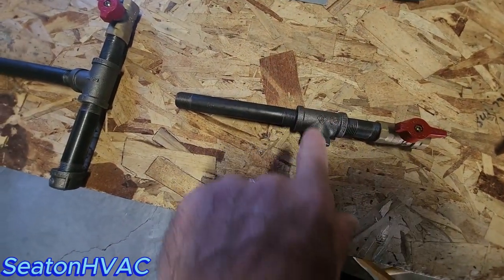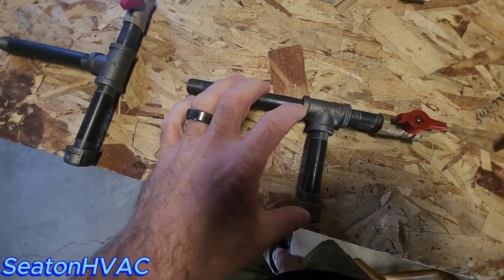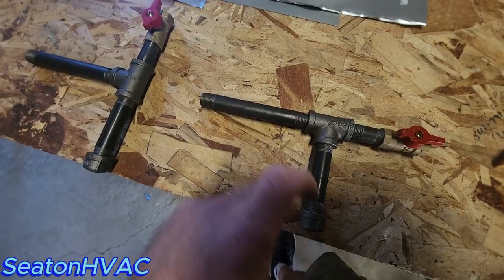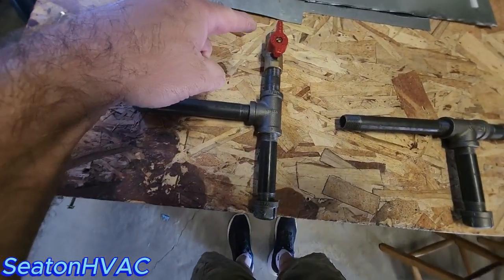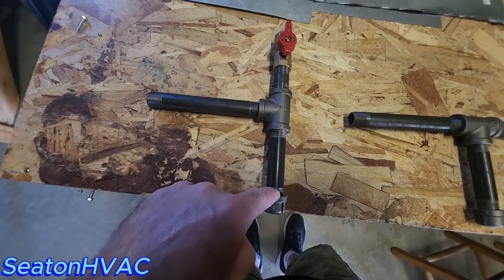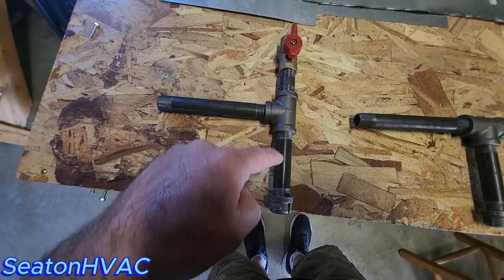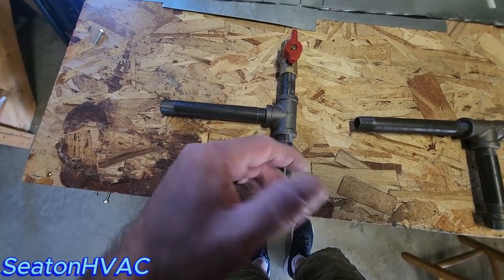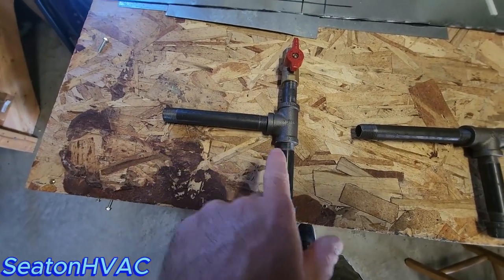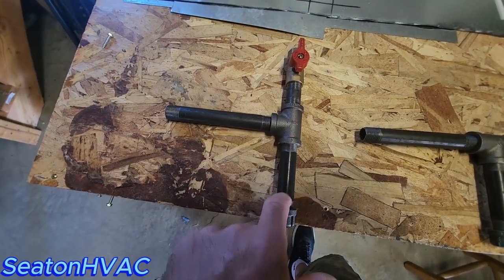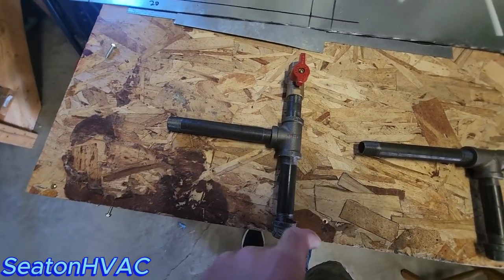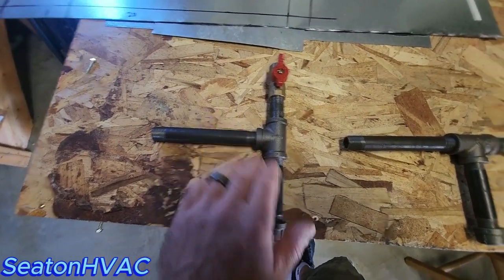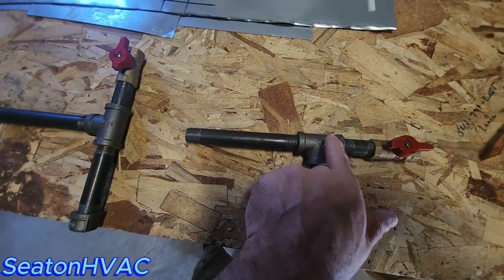You need to have your tee do a change of direction, okay? Your drip leg, in my jurisdiction, has to be at least 4 inches long. What you want it to do is give the sediment somewhere to drop - it's called a dirt leg, not a drip leg, it doesn't drip, it's a sediment trap. So you need it to change direction so the stuff falls through there, and your gas continues to flow without the sediment in it. If you do it the other way, the sediment's just going to pass right by.